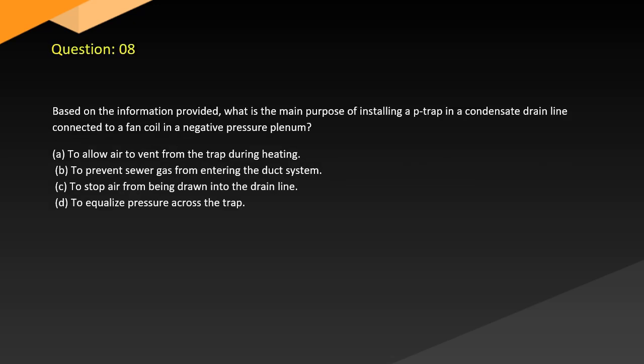Question 8. Based on the information provided, what is the main purpose of installing a P-trap in a condensate drain line connected to a fan coil in a negative pressure plenum? A. To allow air to vent from the trap during heating. B. To prevent sewer gas from entering the duct system. C. To stop air from being drawn into the drain line. D. To equalize pressure across the trap.